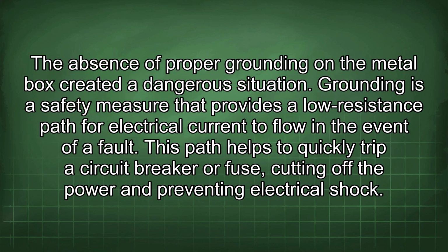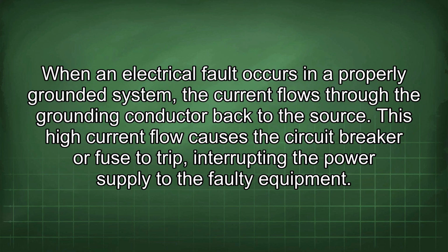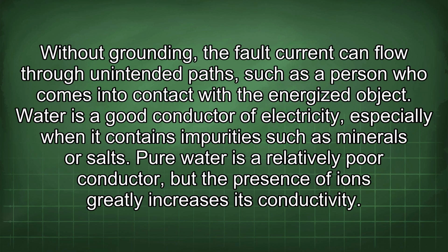The absence of proper grounding on the metal box created a dangerous situation. Grounding is a safety measure that provides a low resistance path for electrical current to flow in the event of a fault. This path helps to quickly trip a circuit breaker or fuse, cutting off the power and preventing electrical shock. When an electrical fault occurs in a properly grounded system, the current flows through the grounding conductor back to the source. This high current flow causes the circuit breaker or fuse to trip, interrupting the power supply to the faulty equipment. Without grounding, the fault current can flow through unintended paths, such as a person who comes into contact with the energized object.